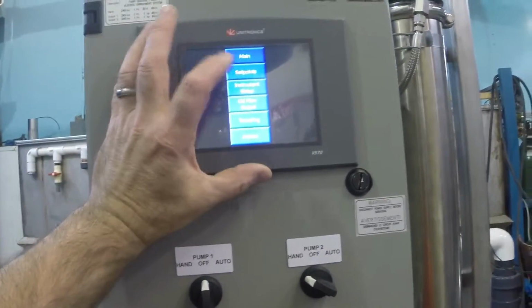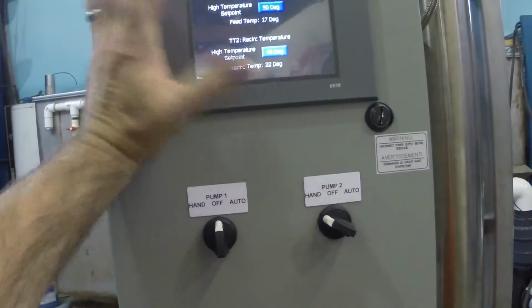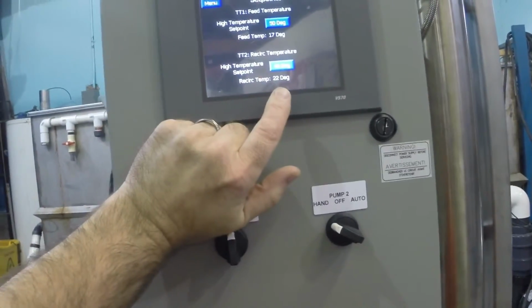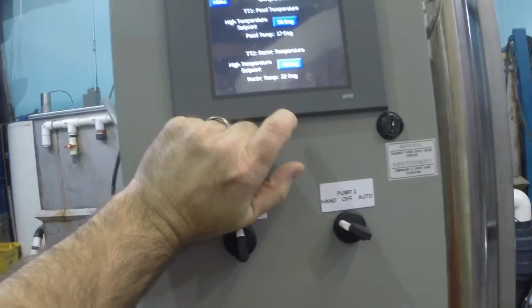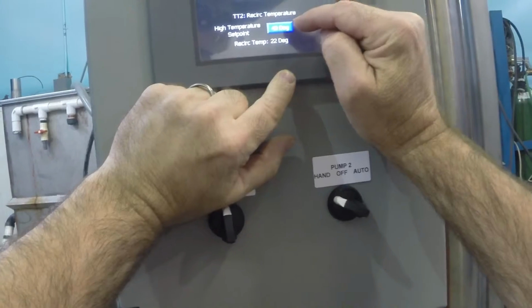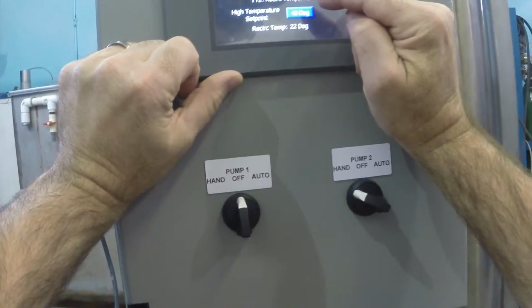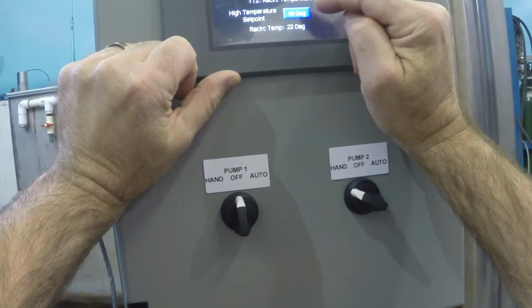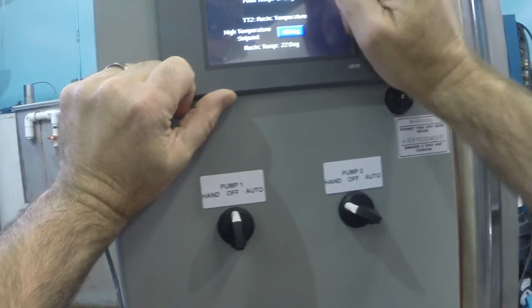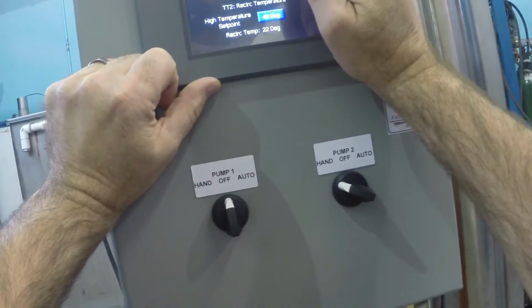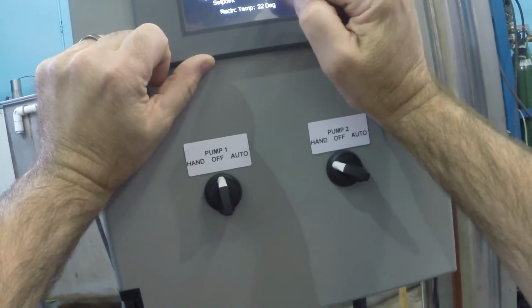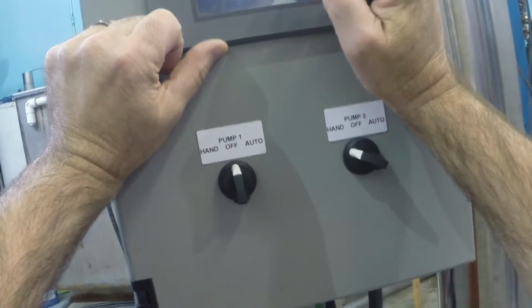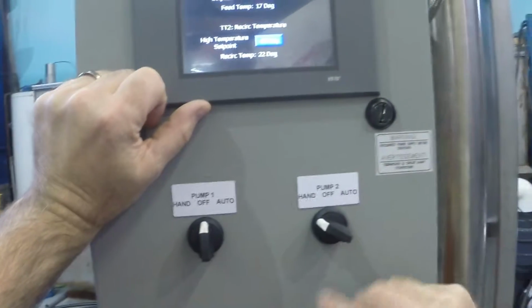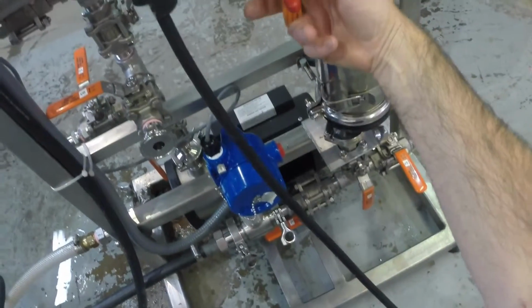Back to menu. You have your set points for your high temperature on each unit. So if your high temperature shut off for your recirc pump, we'll check the manual on that, because the feed temperature, if it's too high, the feed pump will shut off. If the recirc temperature becomes high in the tank, it will start the recirc pump. So right now I've got that deactivated, because this is your sensor right here, which needs to be put into a fitting on the tank.